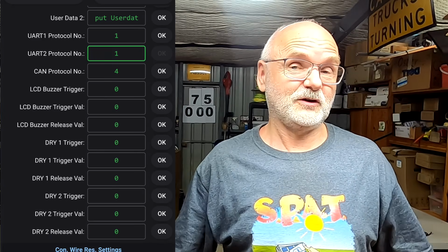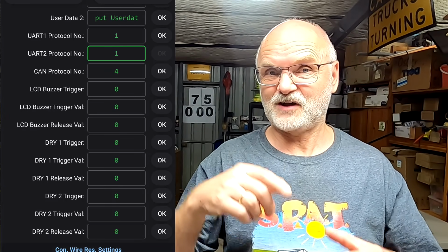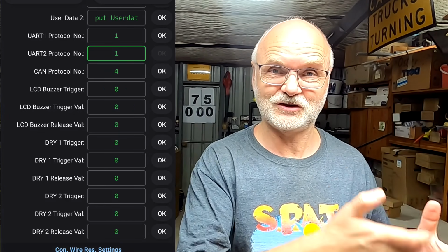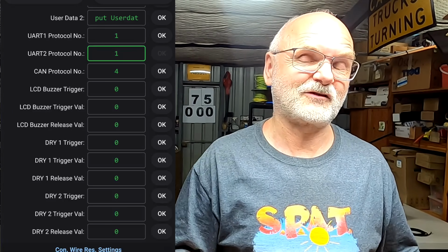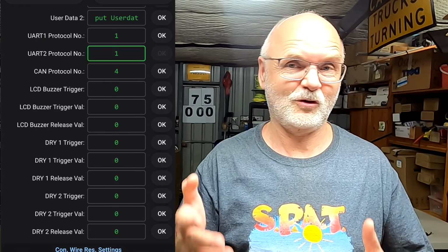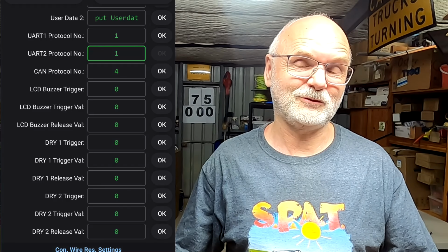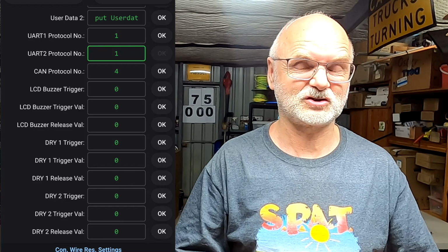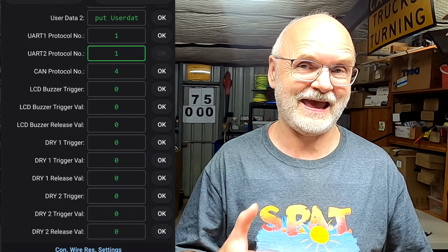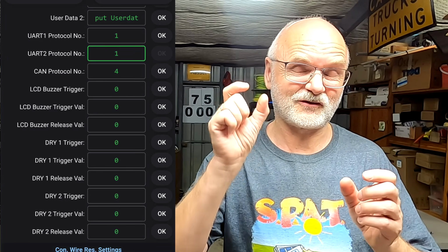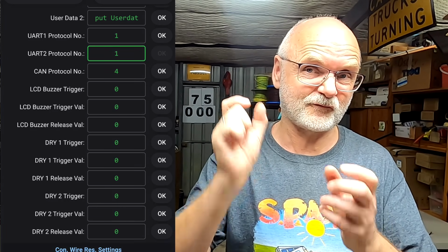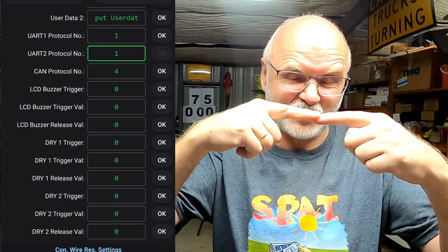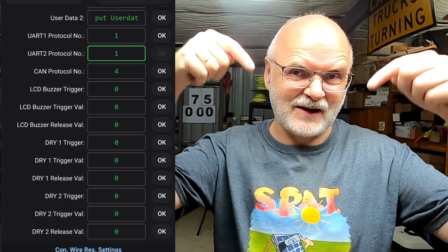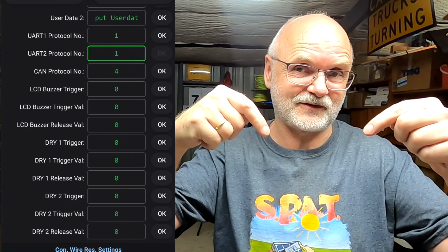Unbelievable. So if your state of charge goes low, you can start a generator, or start charging your battery from the grid. If your battery gets too warm, you can turn on a fan or air conditioning. If one of your battery cells goes over a certain voltage, you can activate another active balancer. Because these are dry contacts, they are potential-free—it just closes a contact in the relay and you can connect whatever you like.